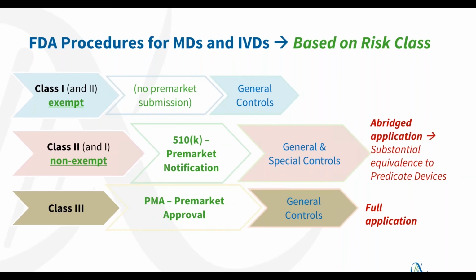The aim of this 510K procedure is that the manufacturer demonstrates substantial equivalence of that device compared to one or more predicate devices. Predicate devices need to be devices already cleared by FDA, commercialized in the United States, and to which our device shares similarities. This is the so-called abridged application applicable to Class 2 devices or Class 1 devices that are non-exempt.